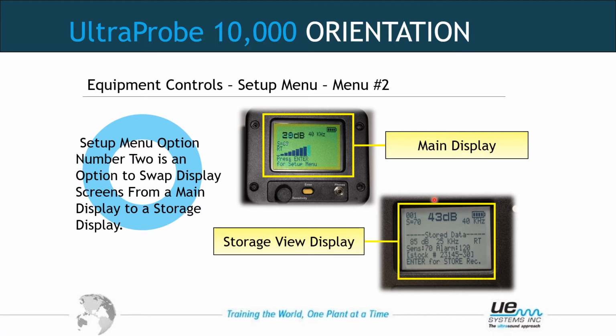This has 4 areas to work through: sensitivity, kilohertz, then your record position is now sitting at the top left of the screen. Whereas on the newer models, you will see your record position sitting to the bottom right on the screen of the main display. You may not access that record from the main display. It's just telling you what record you're on. In the storage display, you may access this. It will go from sensitivity to frequency to record to function bar. So you have 4 cursor areas to work with on the storage display.